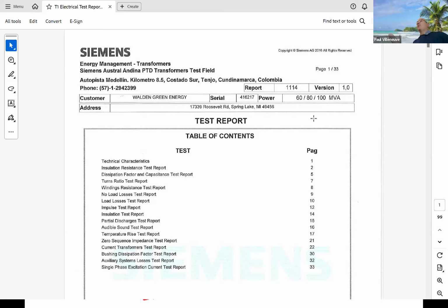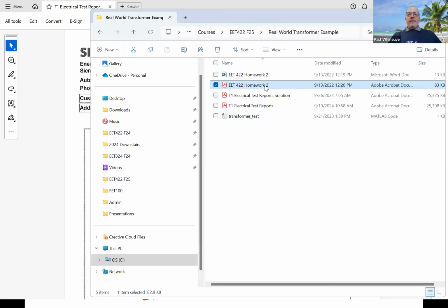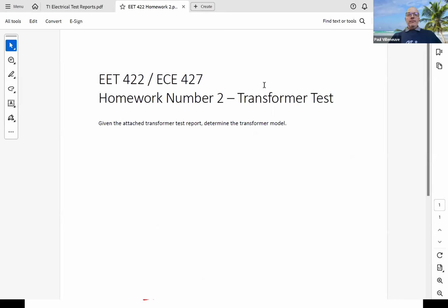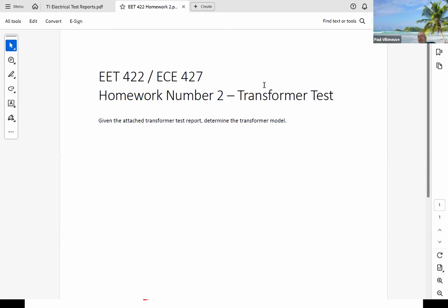Just on the one side of the transformer, you can pick if you want it on the high voltage side or the low voltage side, but I only need to see 4 elements. I don't need to see 6 elements. You should be able to parse through this document and figure out the test information or the test parameters that you need. And it is all in there. You actually have the information that you need to be able to calculate that. Okay, I'll put this test report up there, and then I'll ask you to go ahead and basically do this. Just one problem for your next homework. How's that? Very magnanimous. Any questions on that?